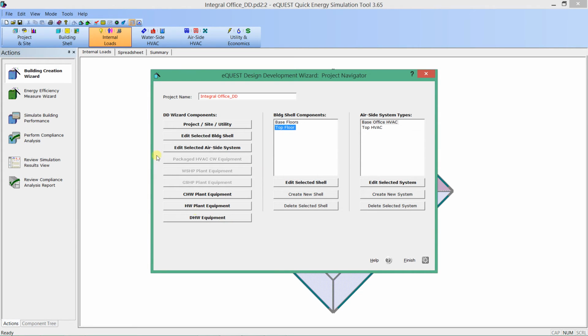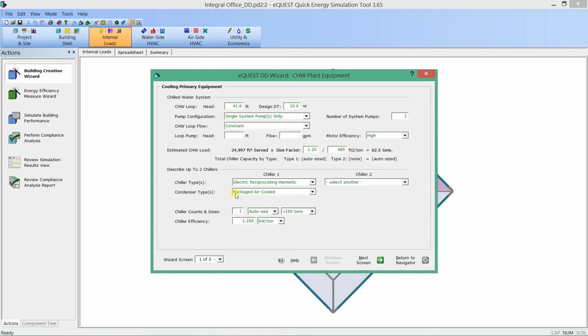And if I felt like it, I could now even go into the shared chilled water plant that they share. Here I can actually see the flow of water can be variable speed. The pump itself can be variable speed control. I can put in, but I don't have to put in, head pressure design or flow. So if an input is not specified, it will actually run anyways, filling in all the blanks as needed. That's the whole point of the wizard mode.